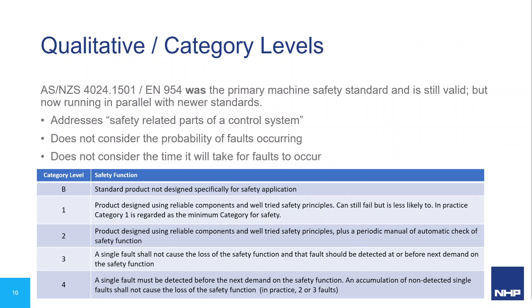It doesn't address things like the probability of faults occurring or the time taken for them to occur. The categories are scaled from least to most effective in reducing risk. Category B is the least effective — mainly characterized by standard components and zero fault tolerance, not necessarily designed for safety applications. Whereas Category 4 uses high levels of fault detection and fault tolerance using redundant components.